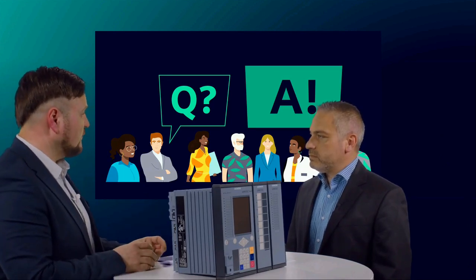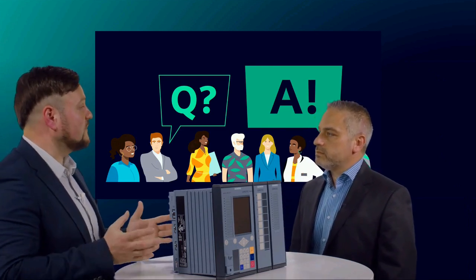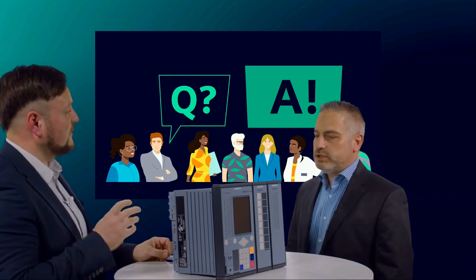There is a difference between an ATS system and an HSBT system. An ATS, automatic transfer system, normally transfers the load from one infeed to another over several seconds, so we use sync check functionality there. A high-speed busbar transfer system works in milliseconds. It may be an overlapping transfer, or have a short interruption, but very brief. For sequential transfer, you could say break before make: we open the incomer, then after a certain time, say 10 milliseconds, we close the alternative incomer. This is the key difference, and it's not something the A8000 can provide.